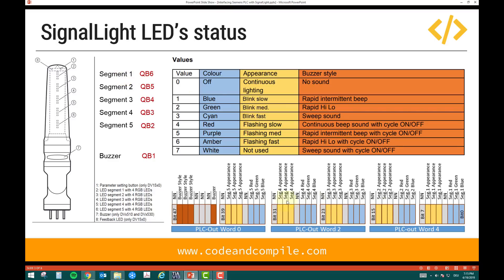Looking at byte QB6 for segment 1, within this byte the first three bits — bit 0, bit 1, and bit 2 — define the color using an RGB combination. The most significant bits — bits 5, 6, and 7 — define the appearance: whether you want the color to blink, flash, or remain stable. If the appearance bits are 0, the color will be stable continuous lighting. If you set it to 1 with blue selected, it will be blue blinking. You can also have blinking slow, blinking medium, blinking fast, or flashing slow, medium, fast, or not used.